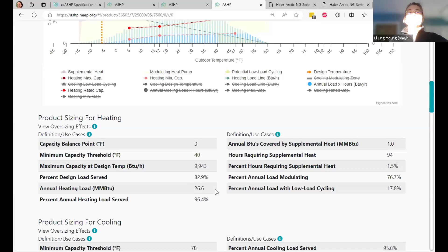I think that this heat pump is a better application for my imaginary building that I'm designing for. However, look what happened up here - this is in the coldest part of the season, and that yellow wedge now is not able to cover all of the heat load under the design conditions. So even though I'm like, oh, this looks like a winner because I have a lot less short cycling, the other thing that's happening is that I lost capacity. It's just too small a heat pump to heat the space over here.